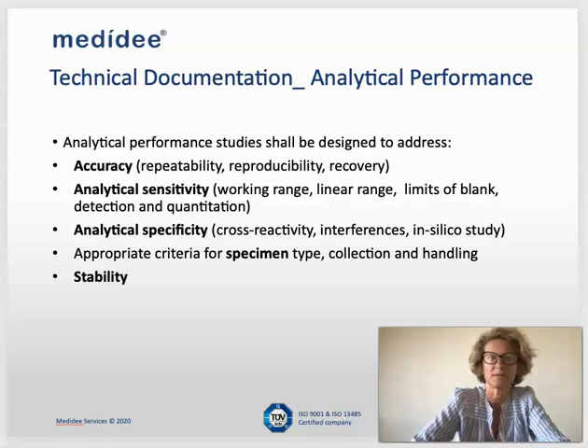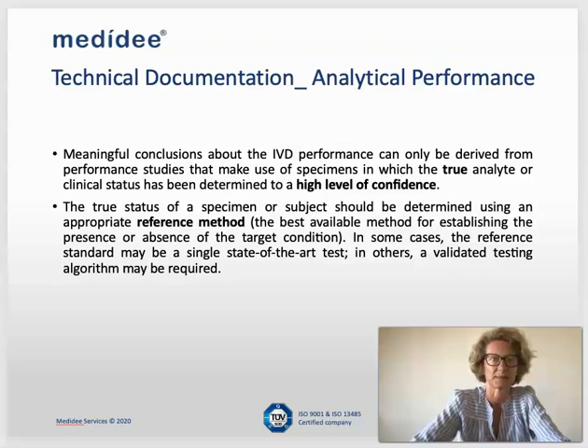When performing analytical performance studies, we have to be sure that we are using specimens, so samples, in which we know the true value of the analyte, meaning that we have to be sure about the characterization of the samples used during the analytical performance studies. When we talk about the characterization of those samples, it means that we need a method which assures us about the trueness of the analyte in those specimens. And normally to do that, we need a reference method. This reference method is normally a state-of-the-art method, or the method which is commonly recognized as being able to measure the analyte that our test is intended to detect.